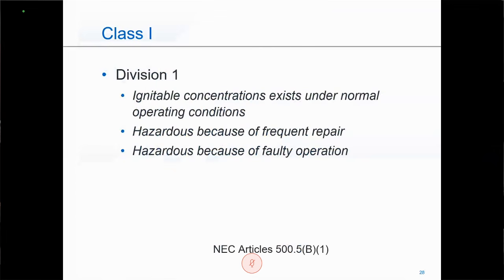So when I have a Class 1, Division 1 area, it's assumed that my gases and vapors are present under normal operating conditions. So when I have this particular area, we're concerned about the gases and vapors that are able to migrate into my electrical products. And we can't prevent this. Conduit threads breathe. When items heat up and cool down, you get vacuum effects. So in a Class 1, Division 1 area, it's assumed that the gases and vapors have migrated into my raceway, into my luminaires, into my receptacles, my switches, all of my electrical equipment.